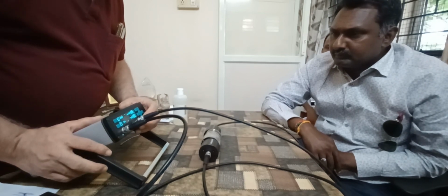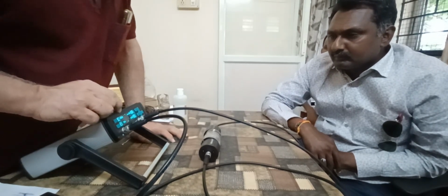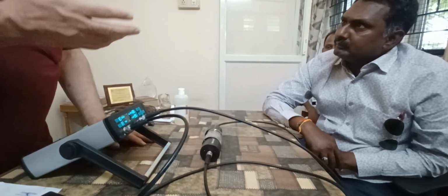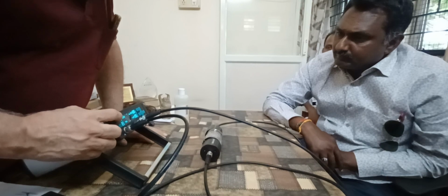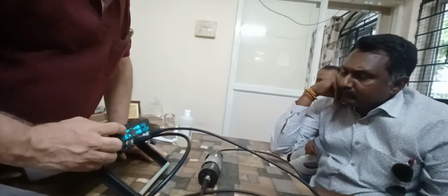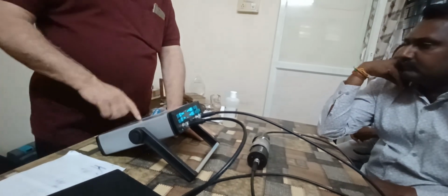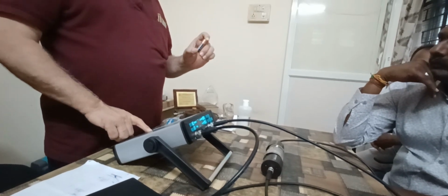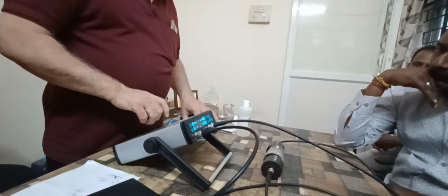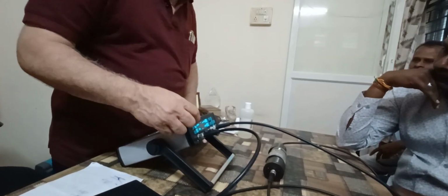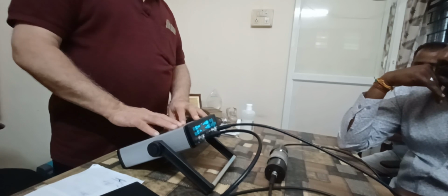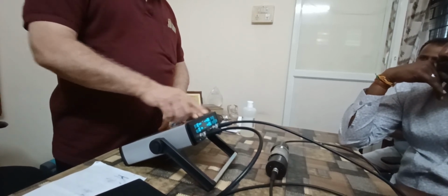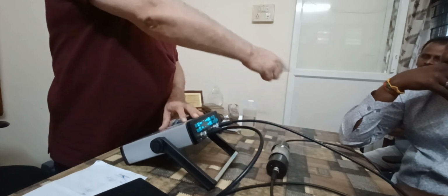I am going there. In the voltage setting, you choose how much voltage you want. It starts from 125 volts, 250 volts, 350, 500 volts. The normal standard setting should be under 500 volts. What we have used in this is four small 1.5 volt batteries, so maximum 6 volts. From this 6 volts, by opting here, this instrument generates 500 volts for the pulse to go inside and come back.